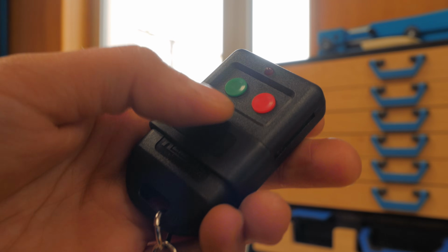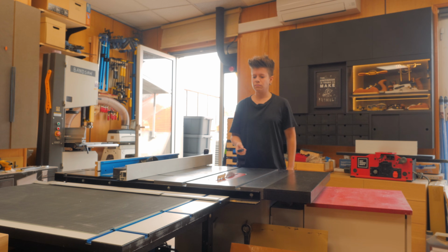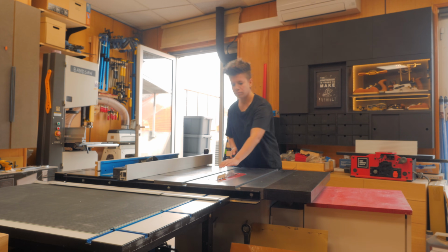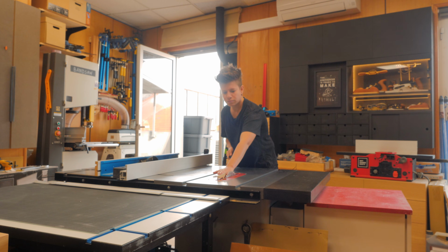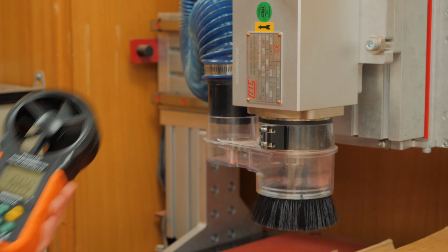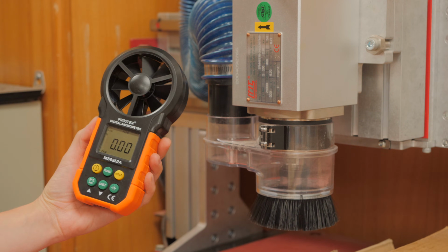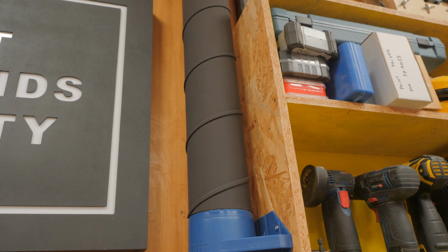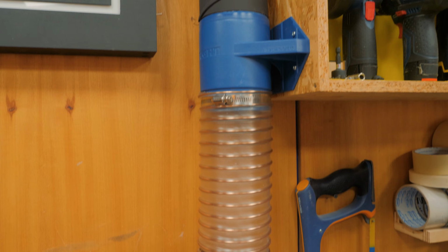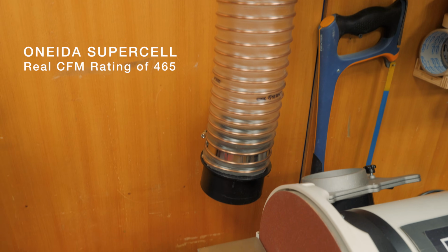It can be remotely turned on and off, and the airflow seems pretty good to feel with my hand. Let's now measure the suction on each port. I purchased an anemometer specifically for this test, and I changed the area value on the device to match each port so we get a truthful CFM number.